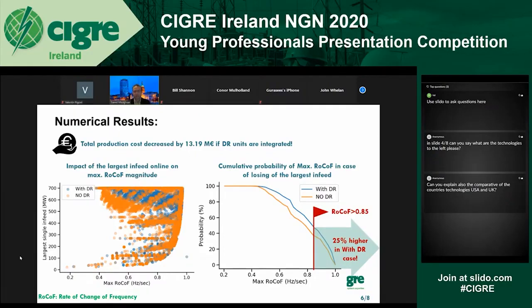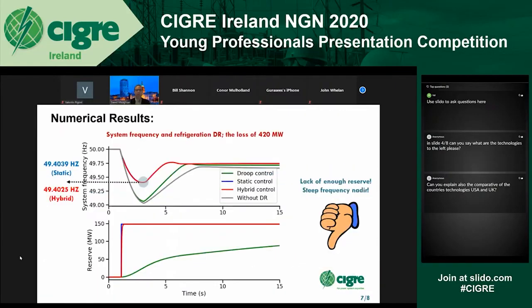In order to show it more clearly, look at the right figure. Its statistical analysis shows that integration of demand response units increases the chance of having a RoCoF higher than 0.85 hertz per second by about 25%. Now, in order to do the frequency stability analysis, a representative summer day with 68% SNSP has been considered.